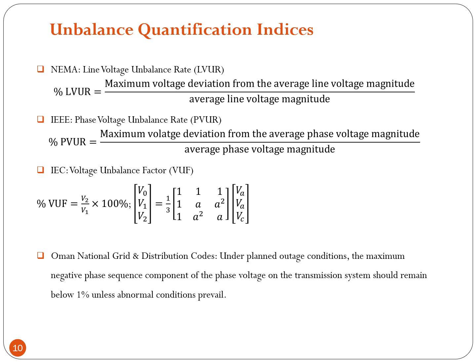The most common definition of unbalanced voltage is the voltage unbalance factor under the International Electrotechnical Commission's IEC, which is known as the voltage components ratio of the negative sequence to the positive sequence. The Oman grid and distribution code uses the voltage unbalance factor, which remains below 1% unless abnormal conditions prevail.